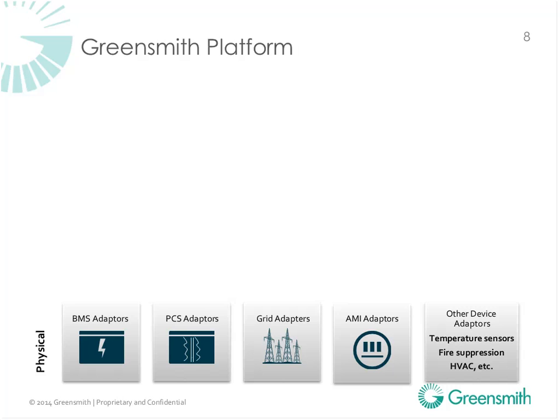One is what I would call the physical layer. We connect to various different battery manufacturers, various different PCS manufacturers—this is the inverter. We connect with SCADA systems and other grid market signals, connecting to AMI systems since this stuff needs to be measured in a revenue grade manner. And then, of course, the safety measures like temperature sensors, fire suppression systems, HVAC systems within the battery module, within the battery container or building.